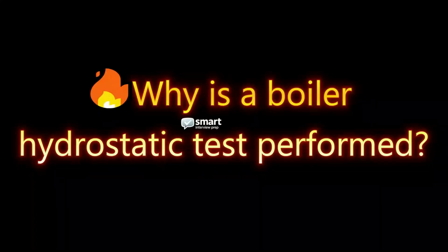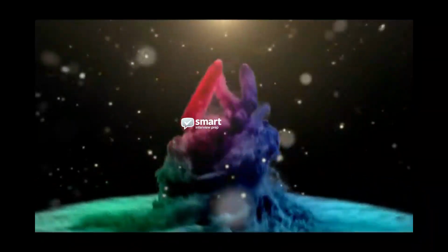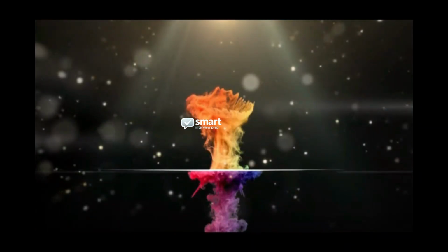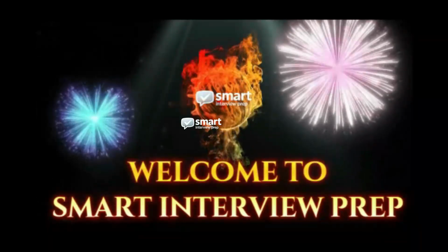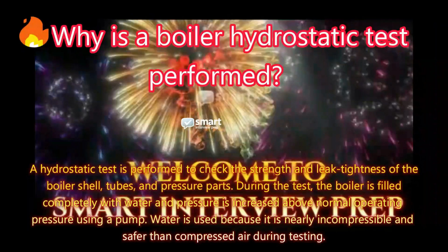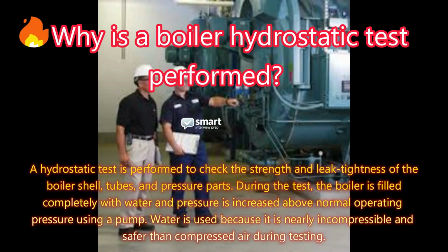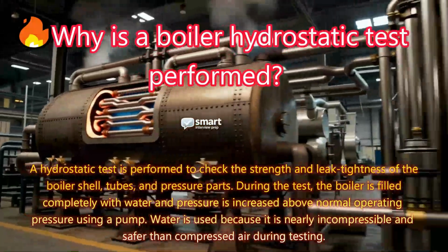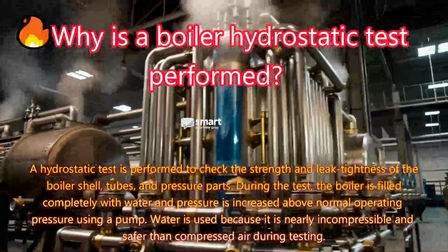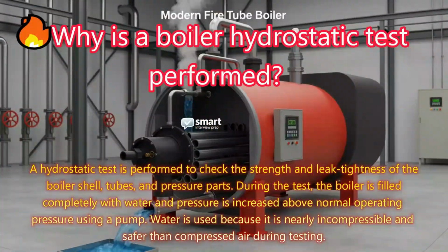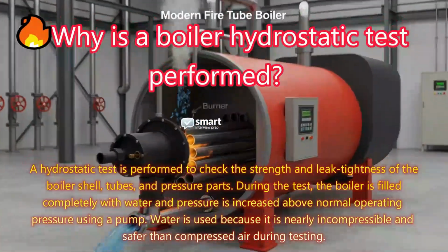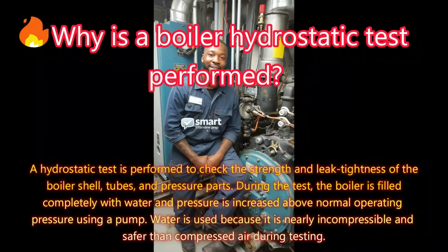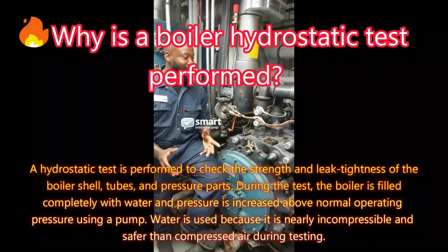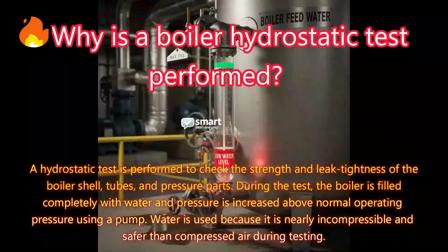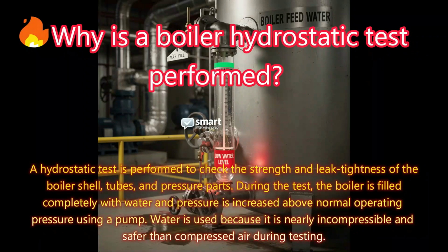Why is a boiler hydrostatic test performed? Answer. A hydrostatic test is performed to check the strength and leak tightness of the boiler shell, tubes, and pressure parts. During the test, the boiler is filled completely with water and pressure is increased above normal operating pressure using a pump. Water is used because it is nearly incompressible and safer than compressed air during testing.